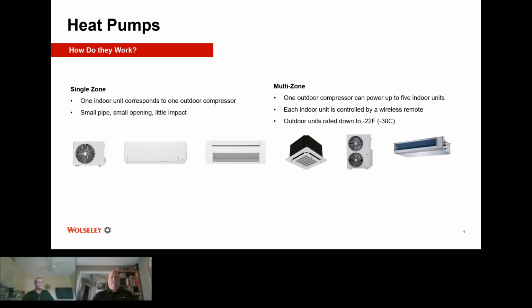Now, how do they work? Well, you've got a single zone that goes one with one, and you've got a small pipe, small opening, little impact as far as installation goes. Multi-zone has one outdoor compressor and can power up to 5 indoor units. Each indoor unit is controlled by a wireless remote, and the outdoor unit is rated down to -30 in this particular case. But you've got to remember that even though it says it's rated for -30, it's not producing 100% of its output. So you've got to check the specs of the unit to see what the true output is at any given temperature.